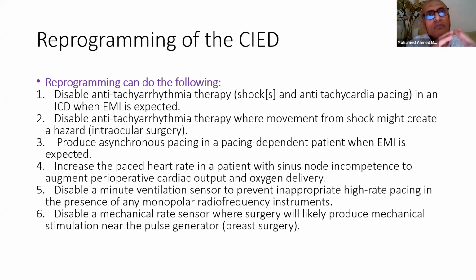In asynchronous mode, the device will not sense any electrical activity, either coming from the heart or coming from the diathermy, and it will ignore all external sensing, and it will pace the heart at a fixed pacing rate.